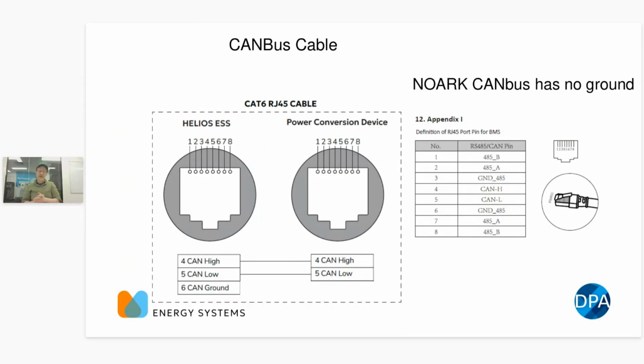Now, I said you could use a straight cable before, but on some of the models of the Noark, not all of them, you actually have to remove pin 6 because you shouldn't be sending the ground through. The reason is that the ground on some of them is the ground for RS485. So the RJ45 plug on the Noark inverters is actually only using one pair for the CAN bus, and another 2 pairs are used for RS485 communications for Modbus. So you can split it out and use it for different things. And it can cause issues if you have that ground from the Helios onto the RS485 ground. I haven't seen it be an issue many times though, but it's just something to be aware of if you have problems.